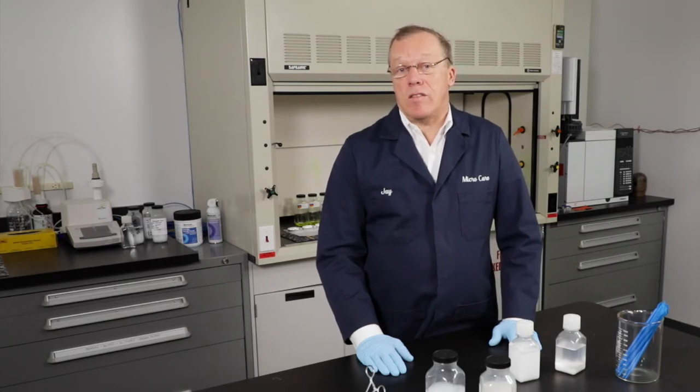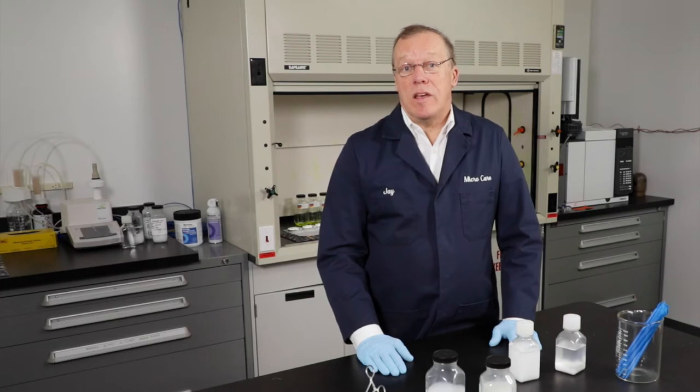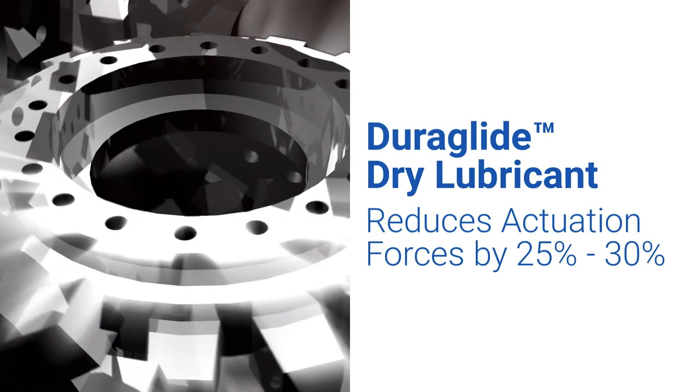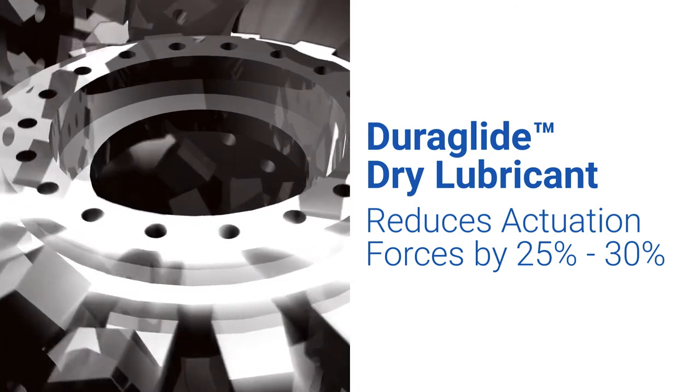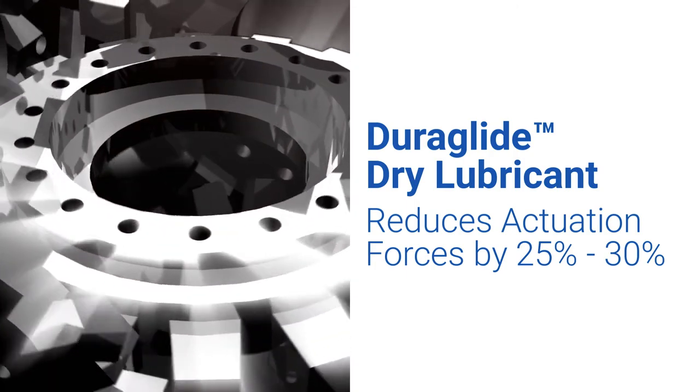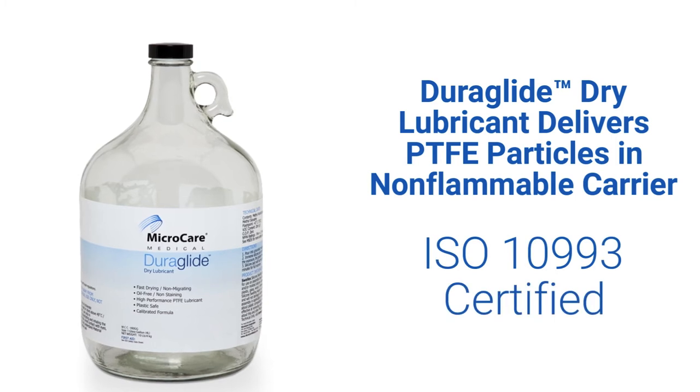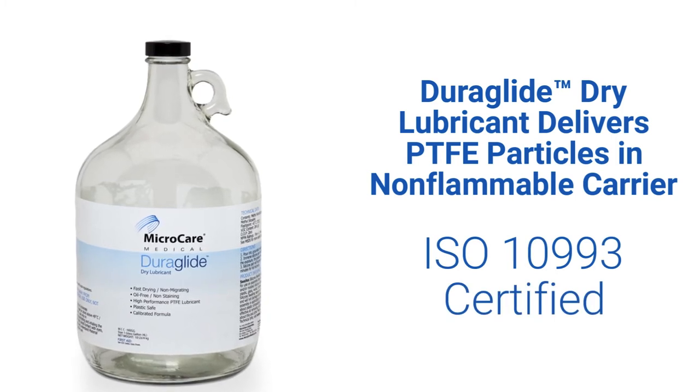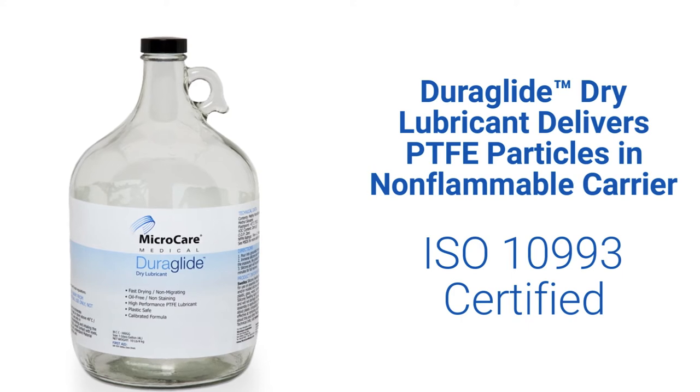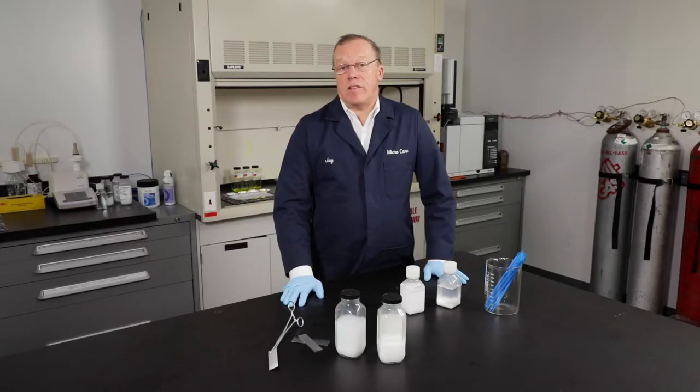MicroCare Medical has developed Duraglide Dry Lubricant to help overcome some of those situations by reducing the actuation forces by 25 to 30%. Duraglide Dry Lubricant is essentially PTFE particles that are held in a dispersion in a non-flammable carrier fluid. It's ISO 10993 tested and certified.